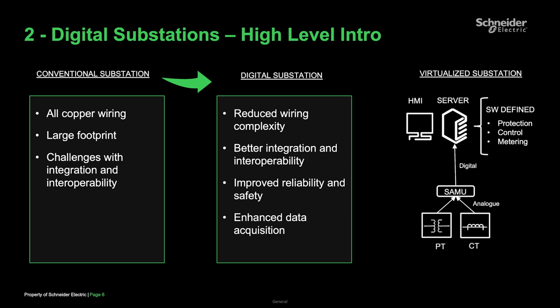So the reduction in wiring complexity, both the copper wiring from the sensors to the panels, but also the wiring inside the panels where you have your IEDs. What it also gives us is better integration and interoperability. We are standardizing on IEC 61850 process bus, so all the devices are communicating and consuming those digital samples using the same protocol.